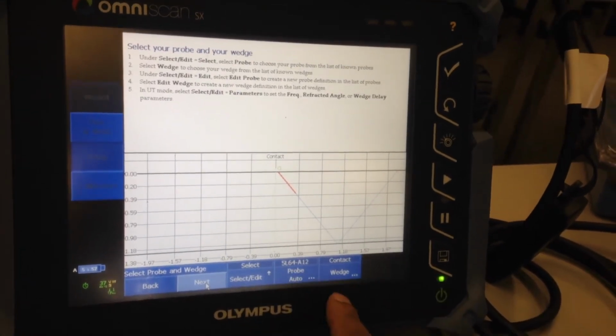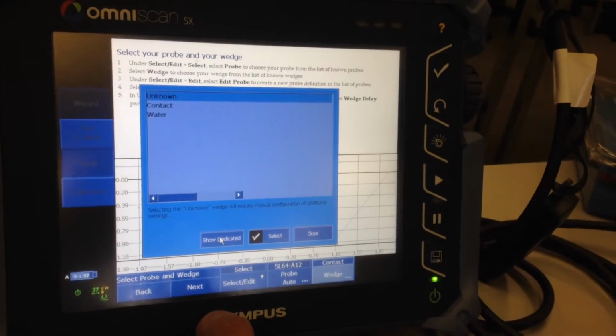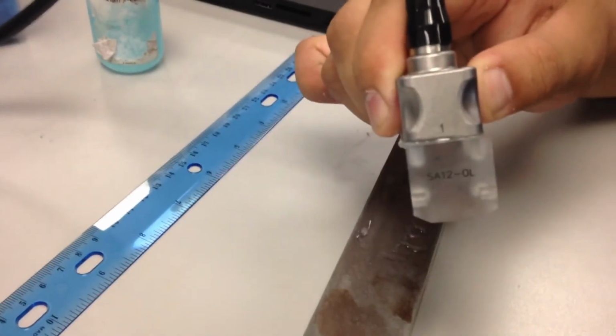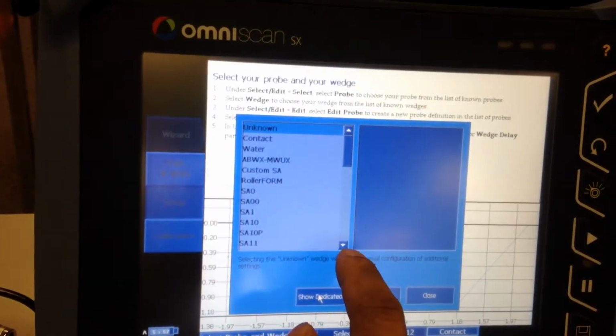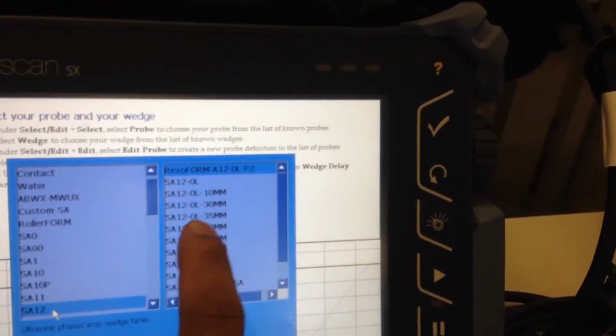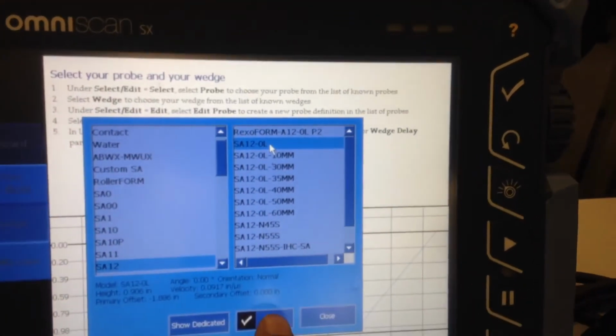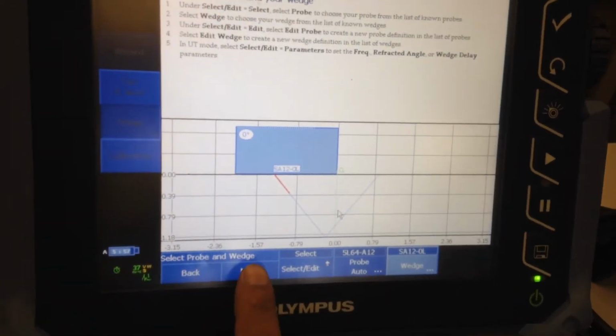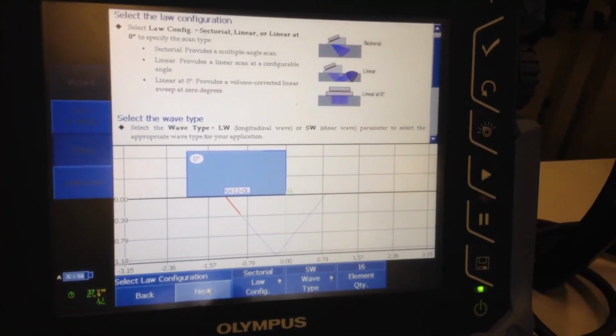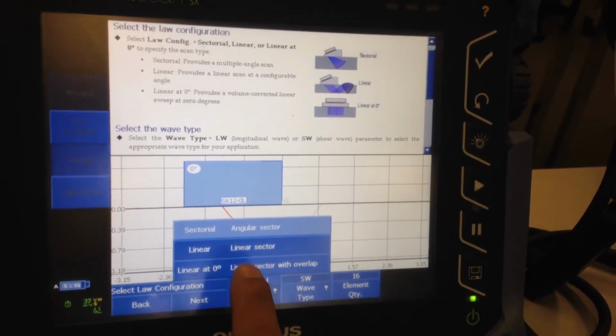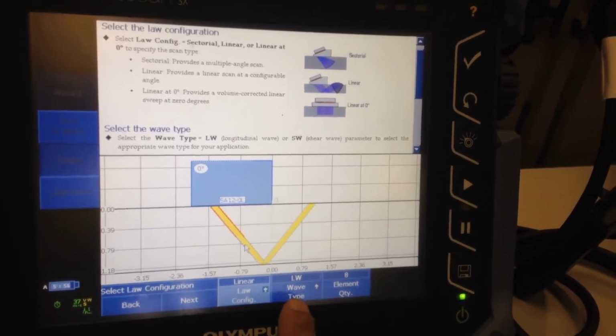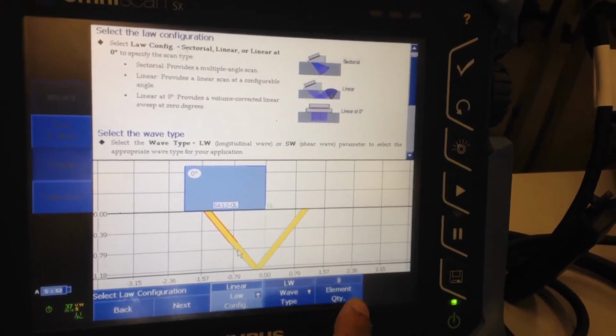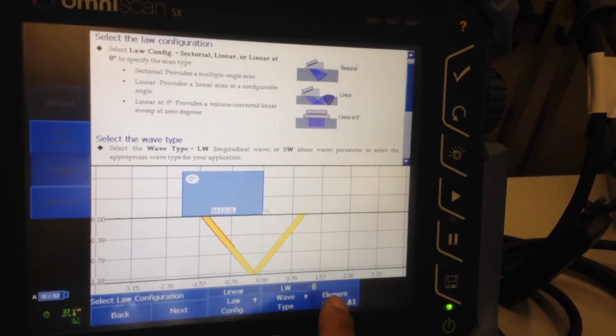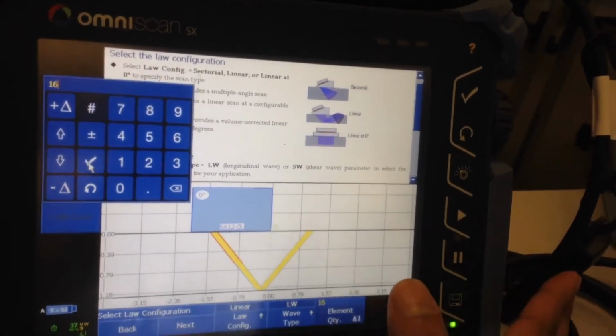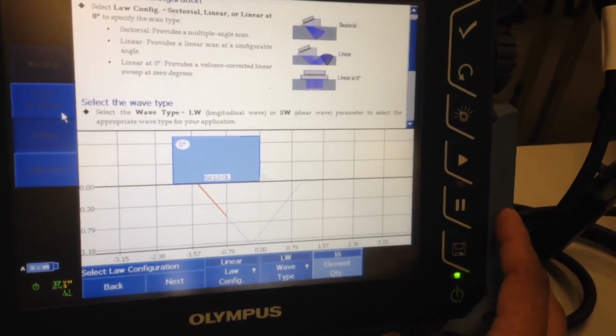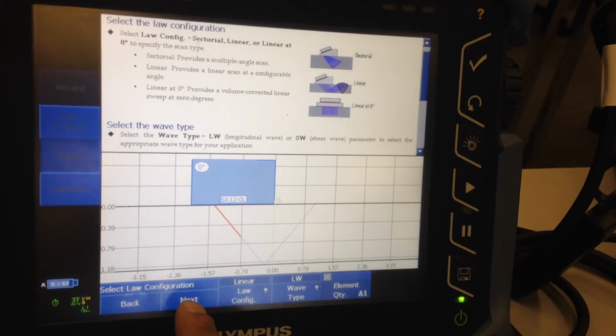Probe is auto selected. Wedge, I will click on Show All, so it opens up the library, and read the numbers off of my wedge, which is SA120L. So I scroll down to SA12 and select 0L, which is 0° linear. Law configuration, leave it on linear sector. Type of wave, longitudinal. Element quantity is 8, and I can use the maximum allowed by my instrument, which in this case has 16 pulsers, so I keep my element quantity on 16. Click Next.